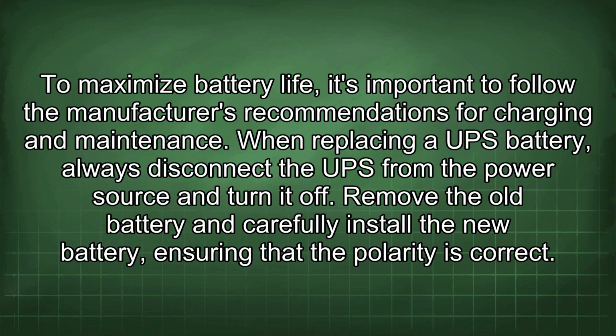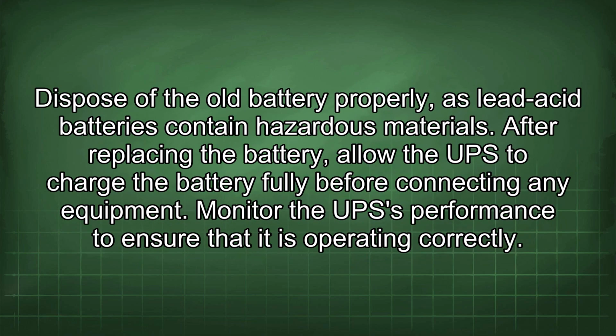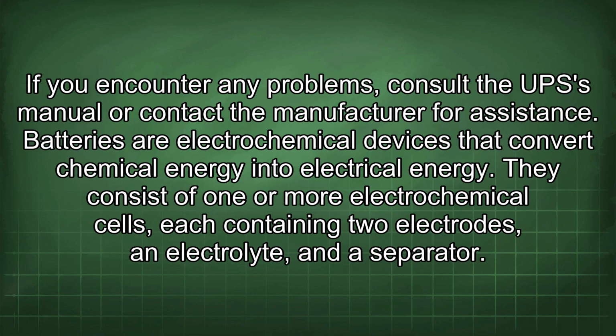When replacing a UPS battery, always disconnect the UPS from the power source and turn it off. Remove the old battery and carefully install the new battery, ensuring that the polarity is correct. Dispose of the old battery properly, as lead-acid batteries contain hazardous materials. After replacing the battery, allow the UPS to charge the battery fully before connecting any equipment. Monitor the UPS performance to ensure that it is operating correctly. If you encounter any problems, consult the UPS manual or contact the manufacturer for assistance.